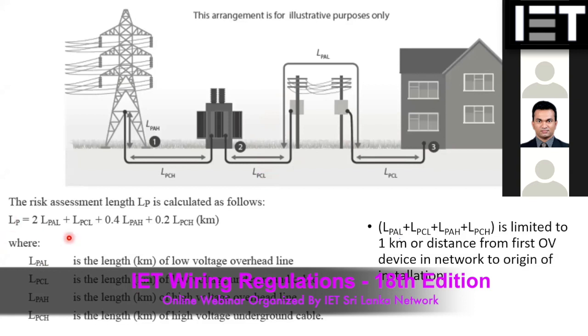When you are calculating that, you consider a maximum length of 1 kilometer. So that is this length component. We are considering only up to 1 kilometer, or whatever location where you have the over voltage protection. For example, on the high voltage side of the distribution transformer, you have the surge protector or the lightning arresters. Then you have to consider the total length from that point to your installation, and even then you should not consider more than 1 kilometer. Maximum is 1 kilometer. The component within 1 kilometer you can put into this equation, and then you can calculate the LP value. So that is the length parameter of the risk calculation.